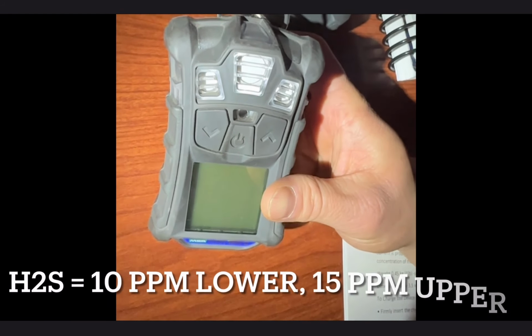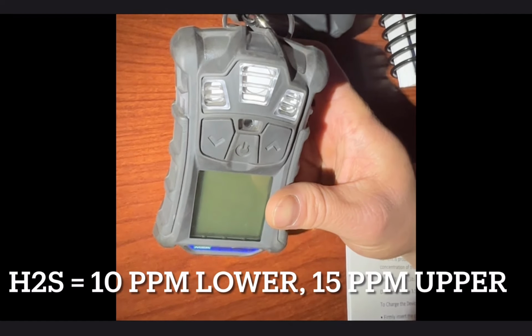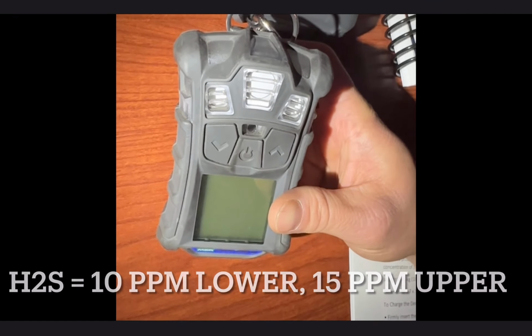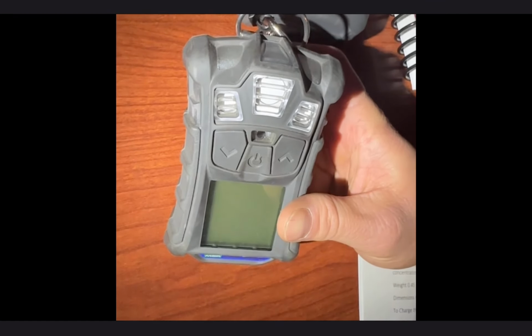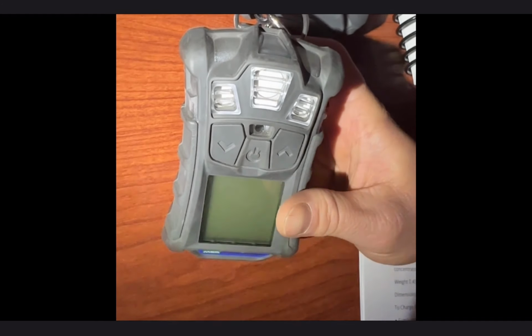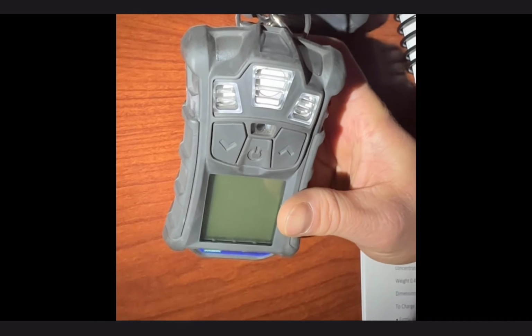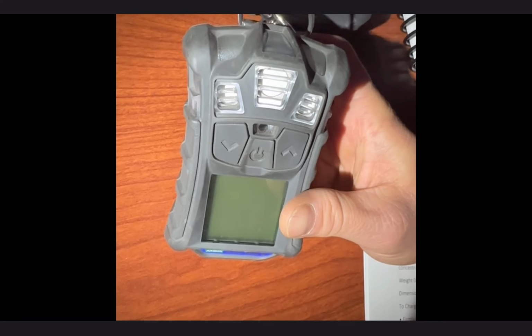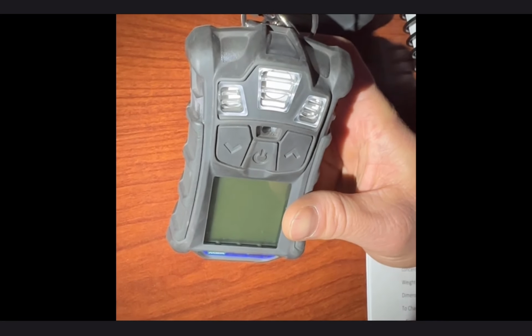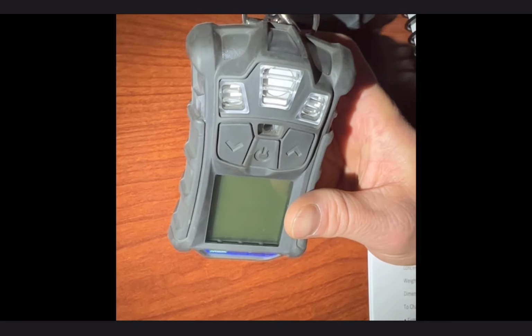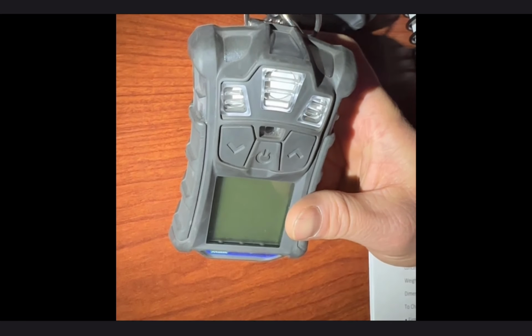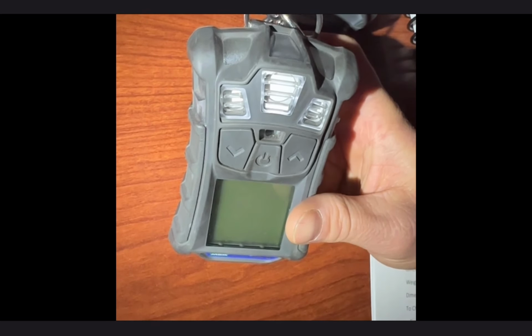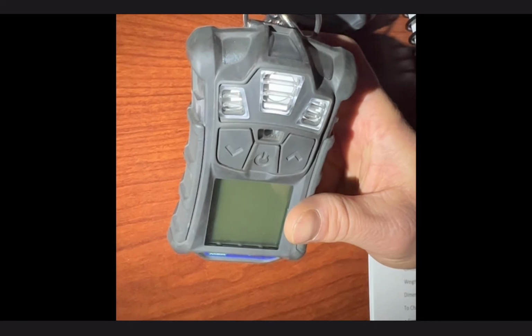H2S, hydrogen sulfide, decomposed materials. The alarm limits are 10 parts per million for the lower alarm and 15 parts per million for the upper alarm, which cues you in that that's a super toxic substance because there's a low parameter range for those alarm limits. And like I said, the H2S and CO being the toxic gases are 1 sensor, so they're measuring both, which is why you have 3 sensors, not 4.